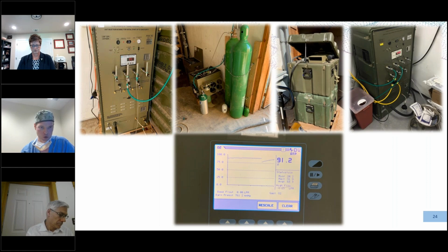You'll notice I have a green hose connected to one of the oxygen outlets. And if you look at the second picture there, that green hose is actually coming down the wall, and that is the booster that I was mentioning. And that booster is plugged into that large H tank, and I am pressurizing that tank, again, up to 2200 PSI. If you look at the bottom picture there, that's my oxygen meter to make sure how much oxygen I'm actually generating there. And at that time, I was generating 91.2% pure oxygen with that generator.